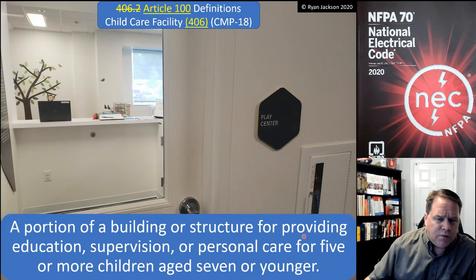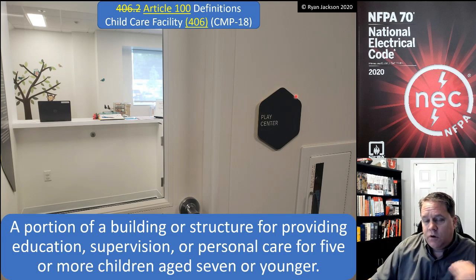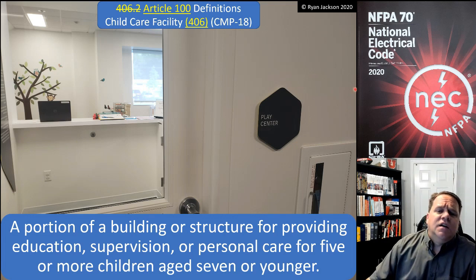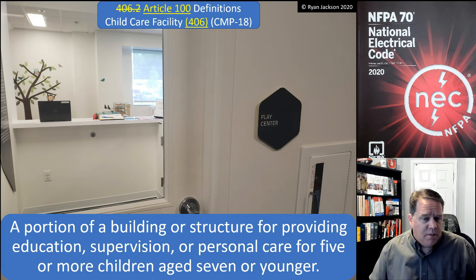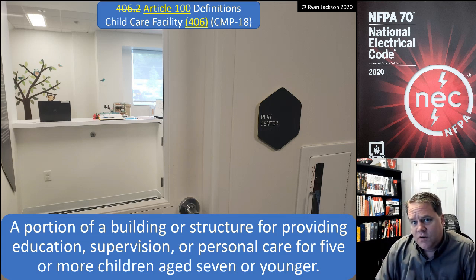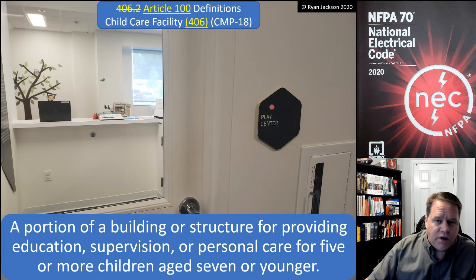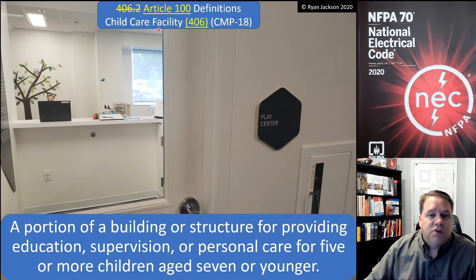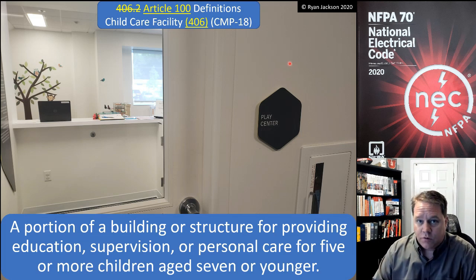Right now, if you want to know the definition of "child care facility," you would go to Article 406, because that's the only place that term is used — in 406.12 for tamper-resistant receptacles, which requires receptacles in child care facilities to be listed as tamper resistant. In the 2023 code, it will all be in Article 100, but they'll also have a parenthetical reference — so it'll say "child care facility" with "406" in parentheses, meaning it's only to be used in Article 406.